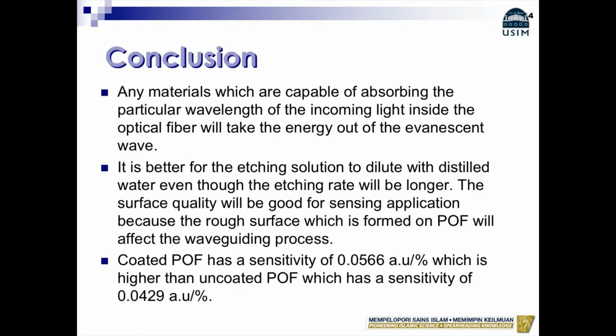The conclusion is that any material which is capable of absorbing the particular wavelength of the incoming light inside the optical fiber will take the energy out of the evanescent wave. So first, it is better for the etching solution to be diluted with distilled water, because we want to make a fiber probe, so we must make sure that the surface quality is good for sensing application. Okay, because it will affect the wave guiding process.